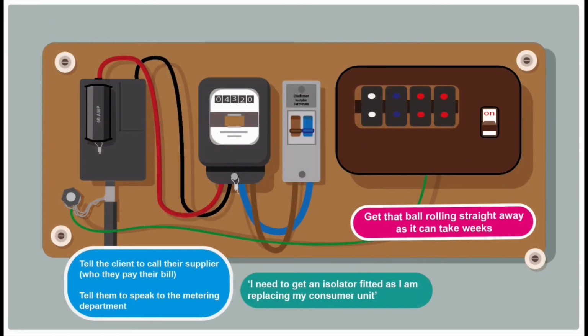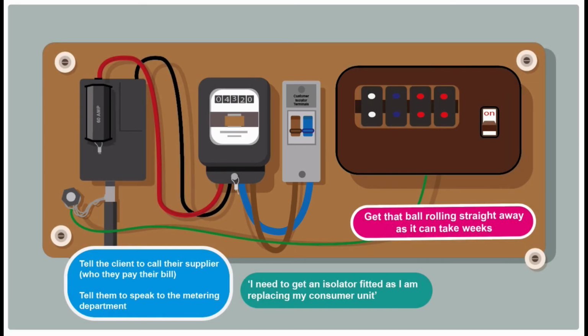Because there was no way of safely isolating this fuse board so we can replace it, we have to get an isolator fitted, pictured here. Now the meter people need to do this and they can take ages to get around to doing it, so you want to get that ball rolling straight away. So you need to tell your client to phone their supplier, the people that they pay the bill to, and get them to speak to the metering department and say that you need an isolator fitted as you're replacing the consumer unit. This can sometimes take ages because the supply companies just think they're there to collect money really. They don't realise they've got a job to do, actually servicing things. So they might get passed backwards and forwards to various different teams before they eventually get to speak to somebody who knows what they're talking about, and they will send somebody round to fit this isolator.